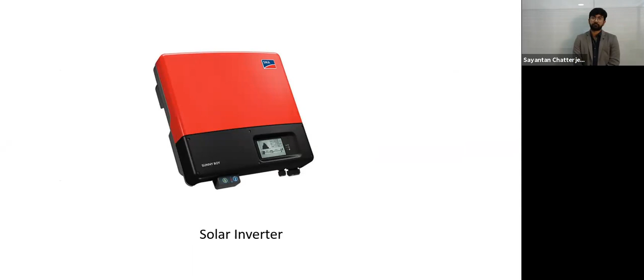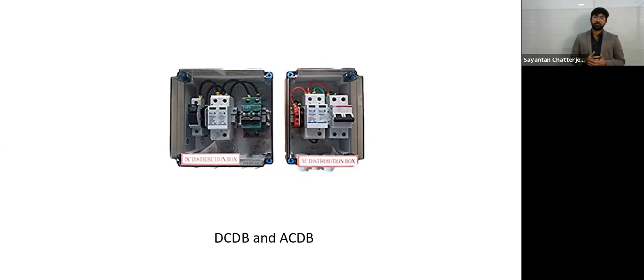These are the DC-DB and AC-DB. Basically, this DC-DB and AC-DB is here for protection, mainly from surges. So from the DC side and AC side, we need to protect the inverter system from surges, using a DC SPD in the DC-DB and an AC side SPD in the AC-DB. For larger scale systems, there is also an isolator and a fuse for every string, so we can isolate every string from this DC-DB.